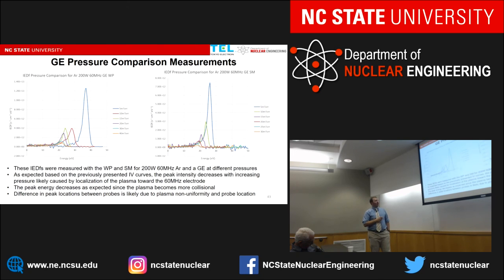Pretty consistent. How does it respond to pressure? Because we were seeing the weird drop in ion saturation current. Well, we see a drop in intensity with increasing pressure between both probes. We also see a decrease in energy, which is what we expect. Higher density, more collisions, you're going to get a decrease in energy. The decrease in intensity is likely due to that localization of the plasma away from the bottom electrode and towards the top electrode.